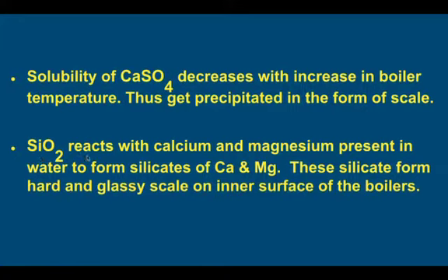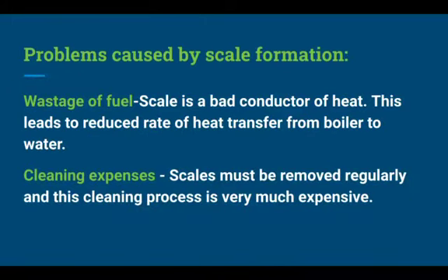Now silica, if present, will react with calcium and magnesium present in water to form silicates of calcium and magnesium. That is, calcium silicate and magnesium silicate will be formed, and these silicates form a hard and glassy scale on the inner surface of the boilers. So this is how calcium bicarbonate, calcium sulfate, magnesium salts if present, and silica can lead to the formation of scales in boilers. Now let us see the problems caused by scale formation.